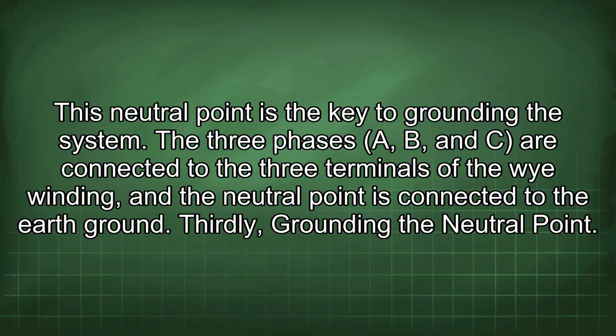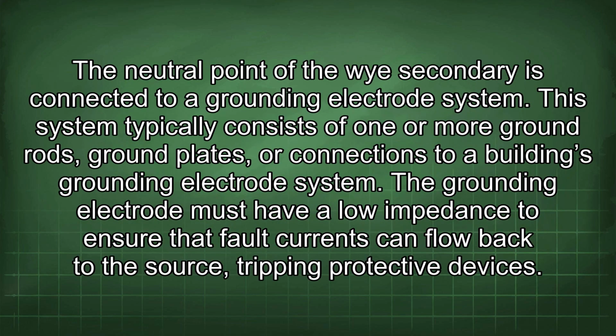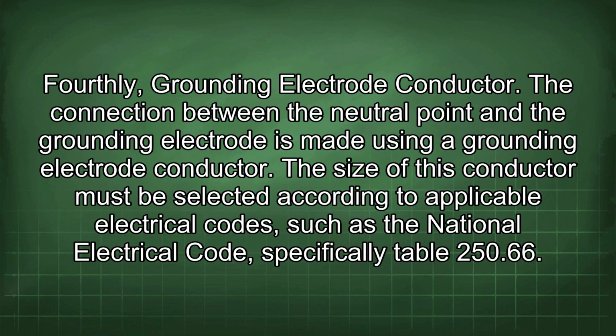Thirdly, grounding the neutral points. The neutral point of the Y secondary is connected to a grounding electrode system. This system typically consists of one or more ground rods, ground plates, or connections to a building's grounding electrode system. The grounding electrode must have a low impedance to ensure that fault currents can flow back to the source, tripping protective devices.